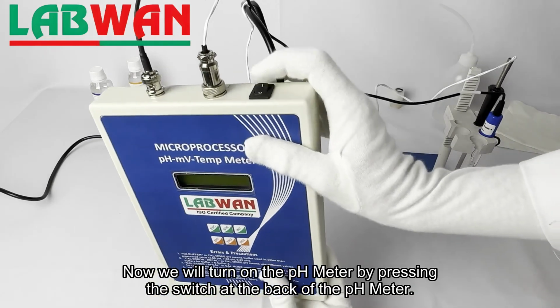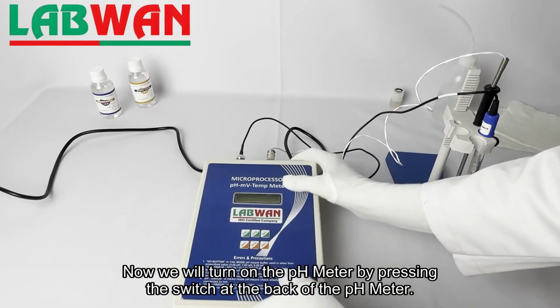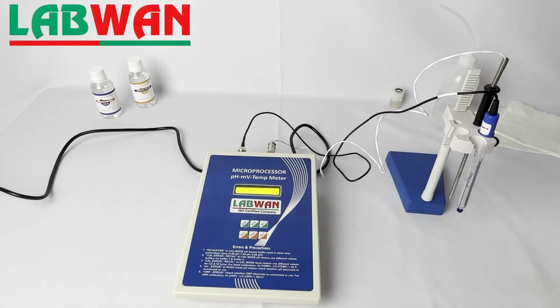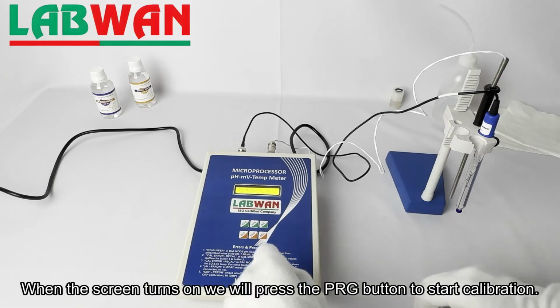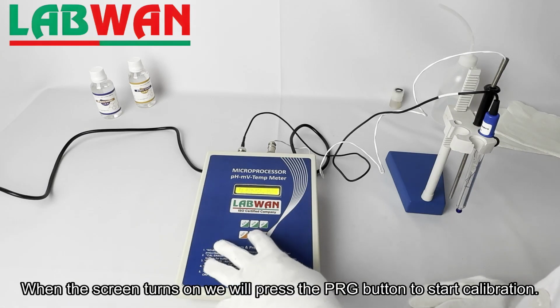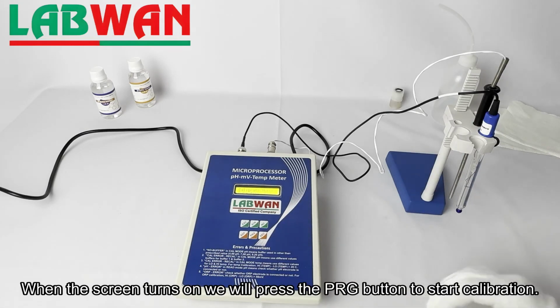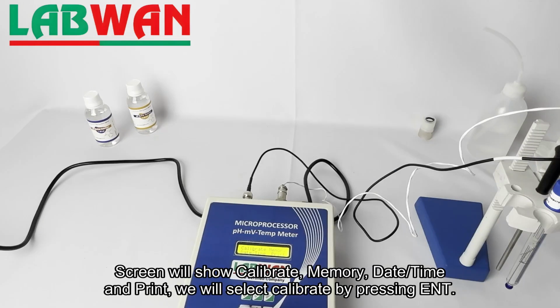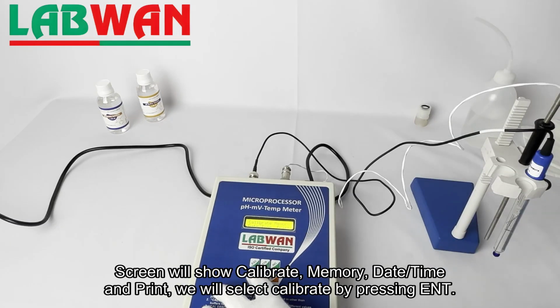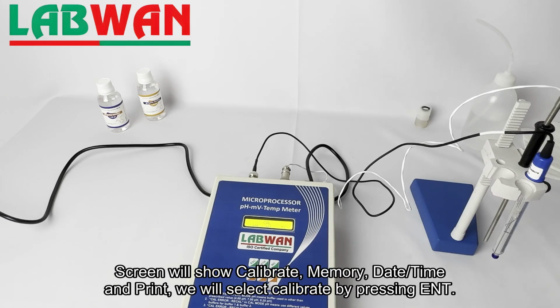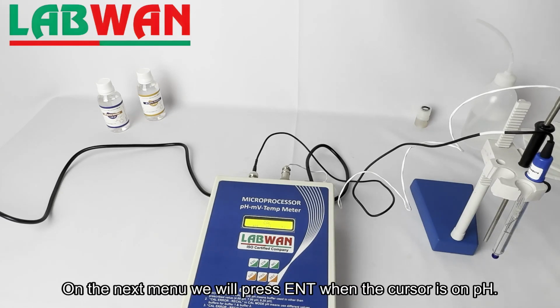Now we will turn on the pH meter by pressing the switch at the back of the pH meter. When the screen turns on we will press the PRG button to start calibration. Screen will show Calibrate, memory, date, time and print. We will select Calibrate by pressing ENT. On the next menu we will press ENT when the cursor is on pH.